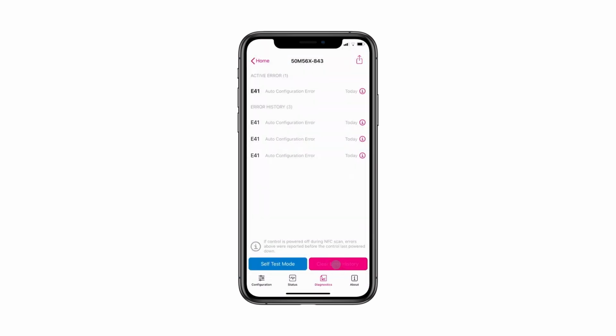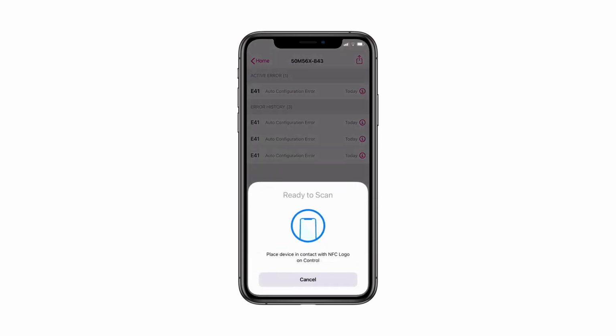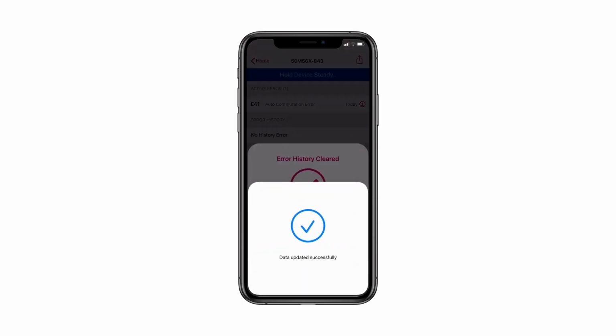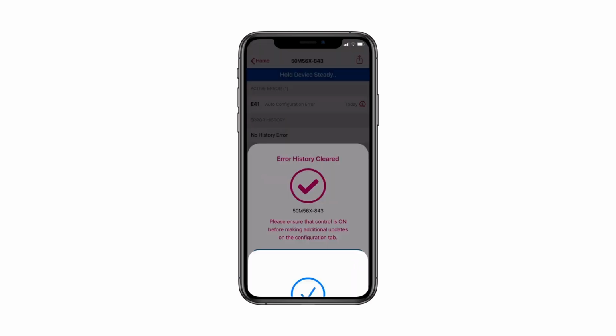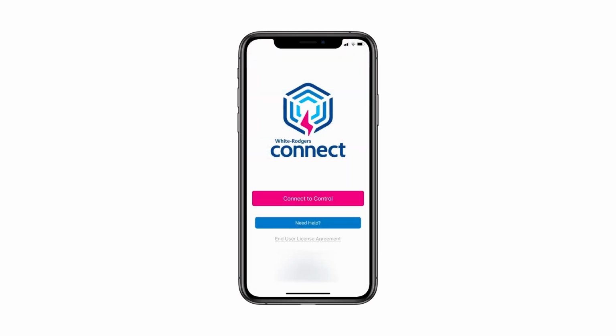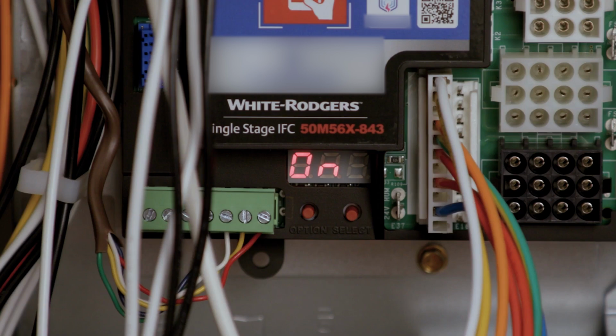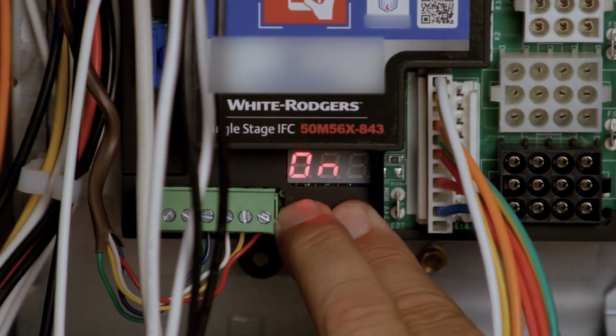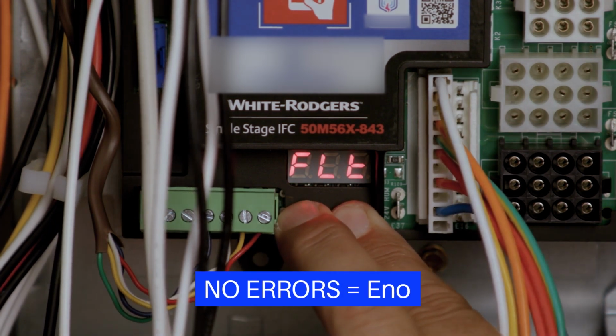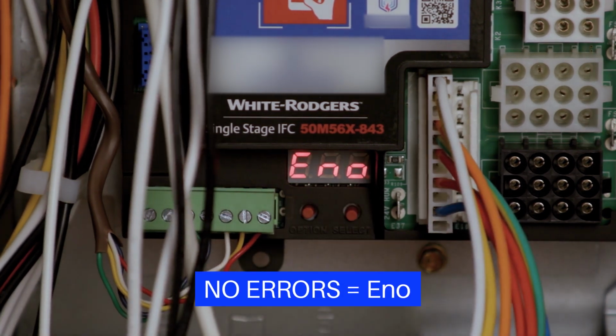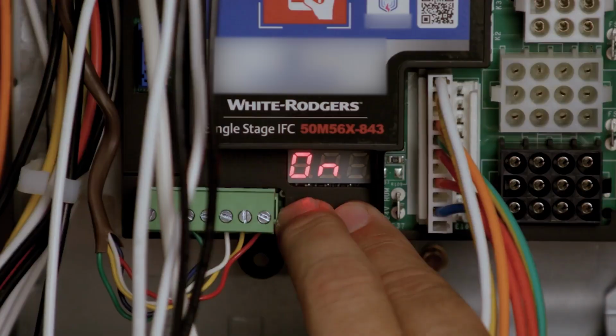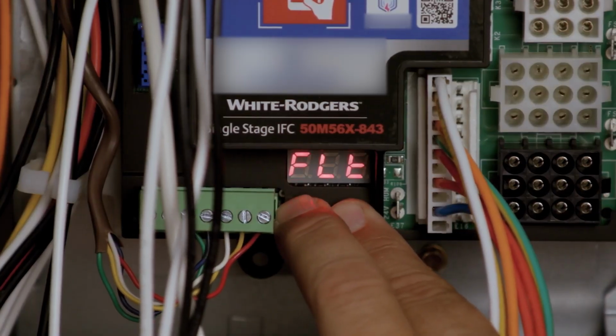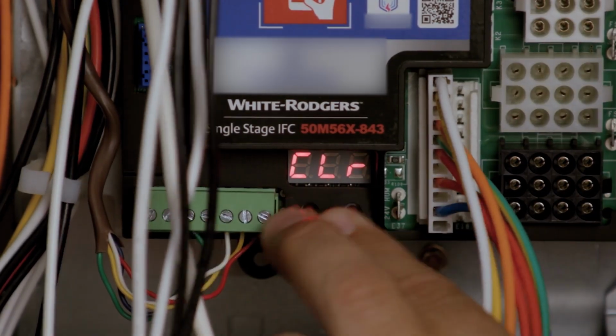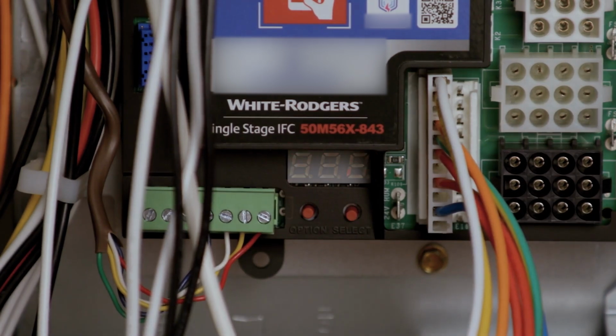To clear errors in the app, tap the Clear Error History button, place the device in contact with the NFC logo on the module, and wait for the check mark to appear. This action can be performed whether the module is powered on or powered off. Fault codes can also be accessed on the module anytime the module is powered. Press the Option and Select buttons for 2 to 5 seconds. If there are no errors, the display will read E and O. To clear errors using the module, hold the Option and Select buttons together for 5 to 10 seconds. This action can be performed whenever the control is powered on.